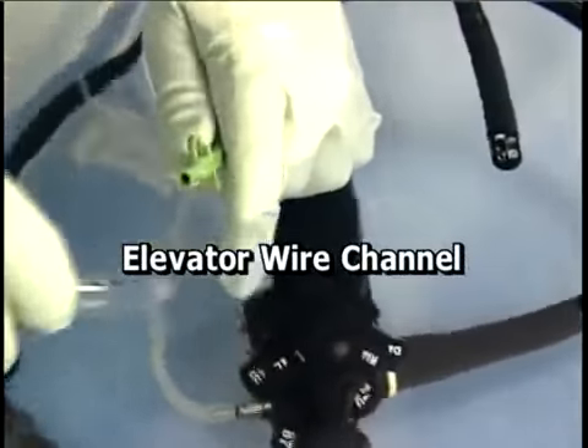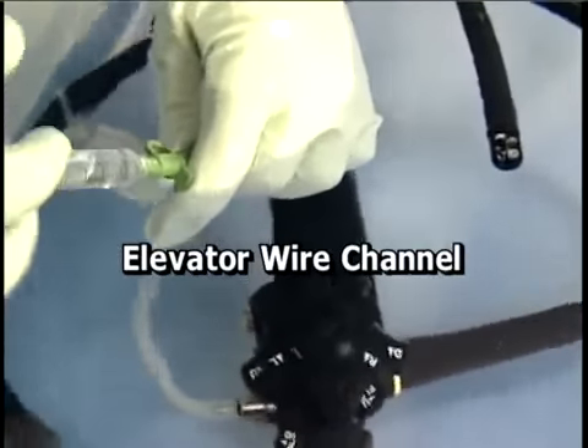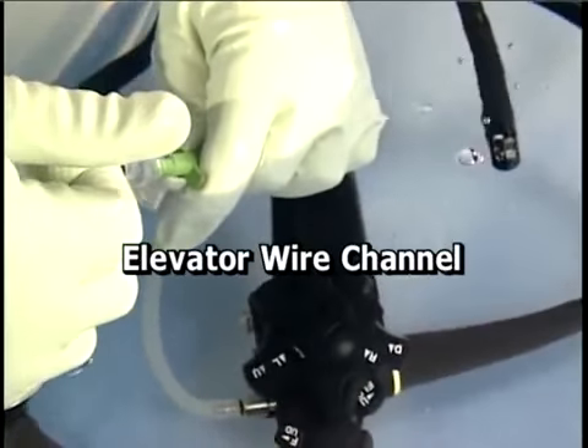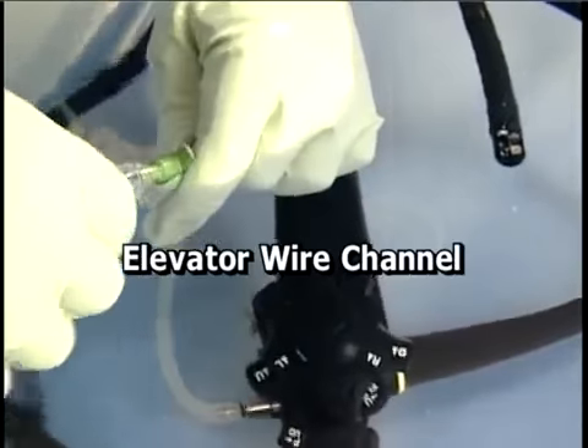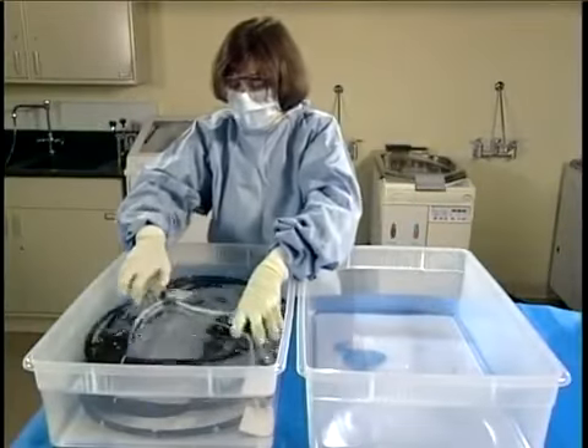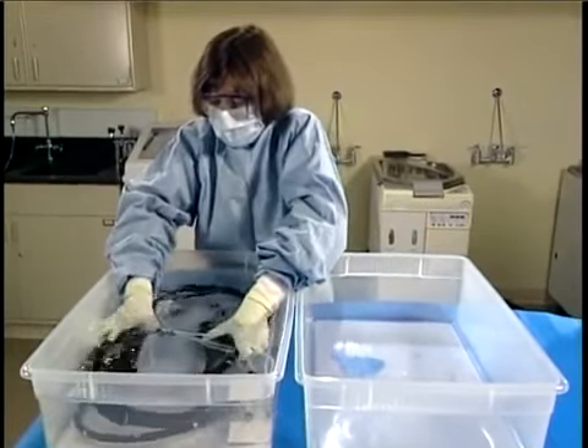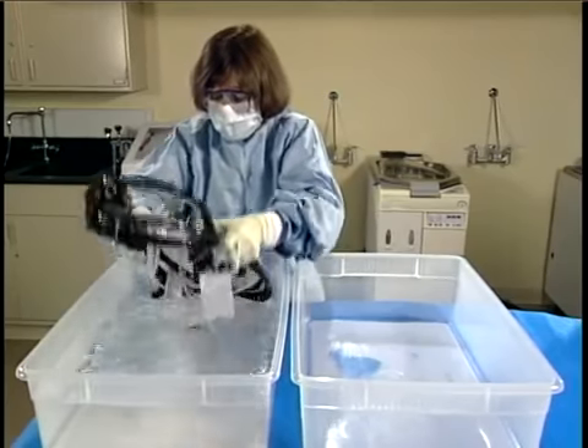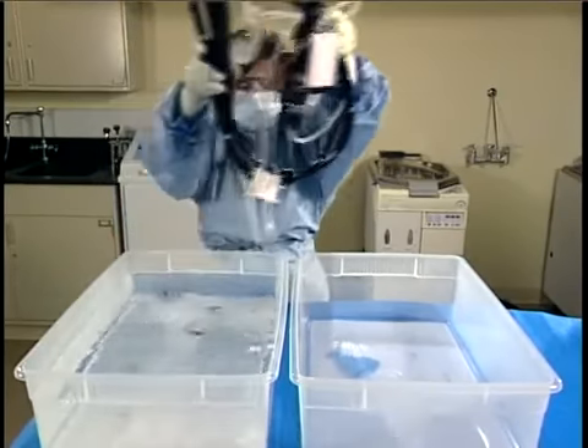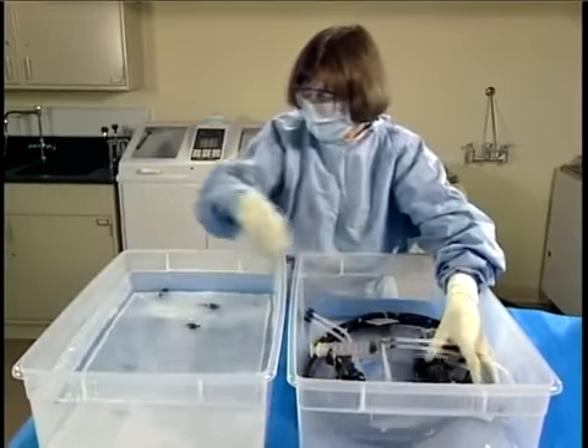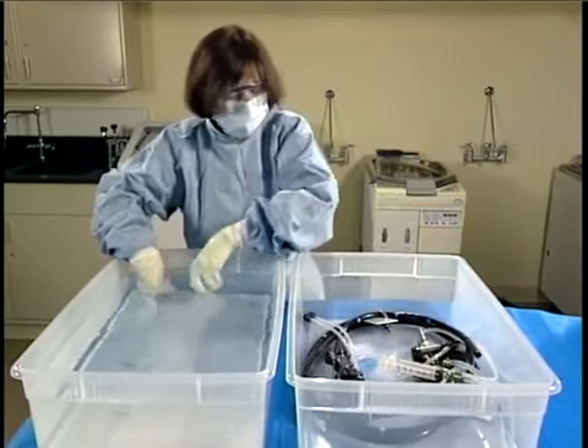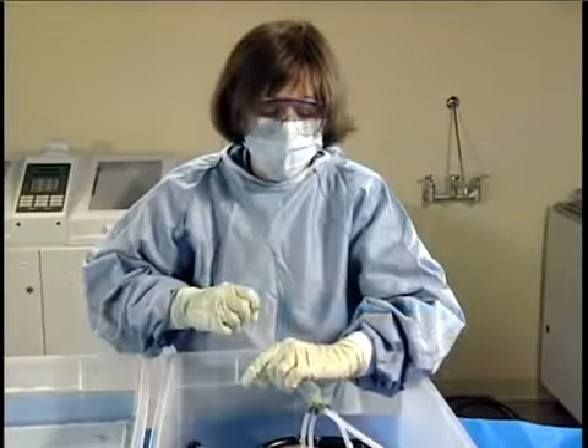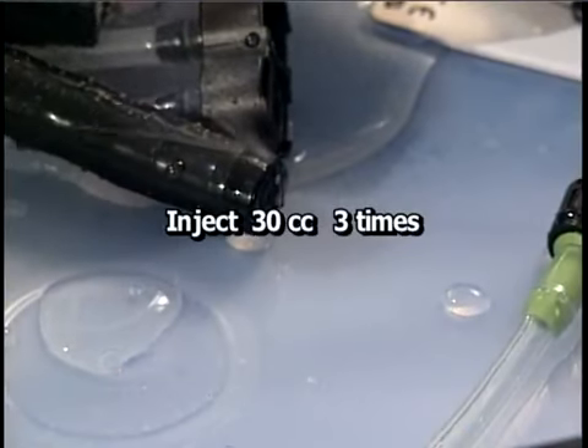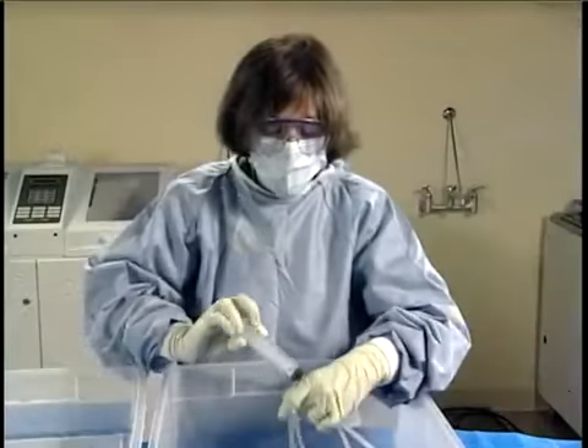If you are reprocessing a duodenoscope, use a syringe to inject water into the elevator wire channel. The next step is to purge the channels with air to remove the rinse water. Transfer the endoscope and accessories to an empty basin. Use the syringe to flush 90 cc's of air through the air-water channels. Repeat this process for the suction channel.